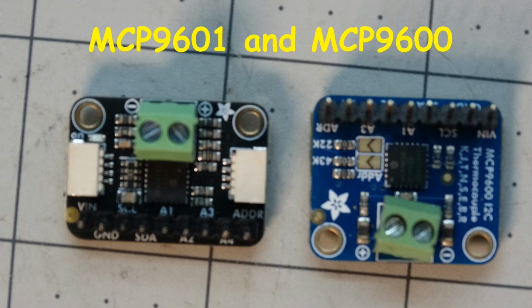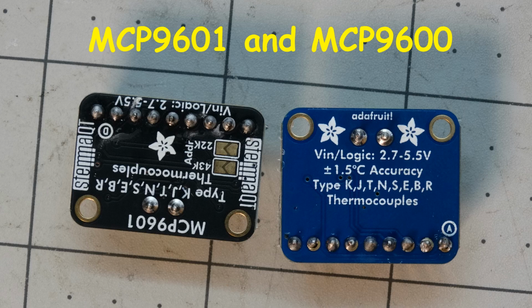Here is a photo of these offending devices. They work pretty well until they don't. And when you do a loop scan on them, they report back only once, which, if you have an installed device, is rather problematic. And I'm never sure when these are going to fail. I still have some in operation, but I'm not going to use very many more of these.